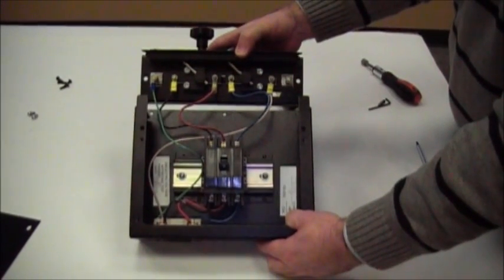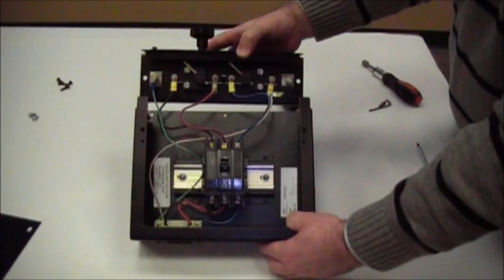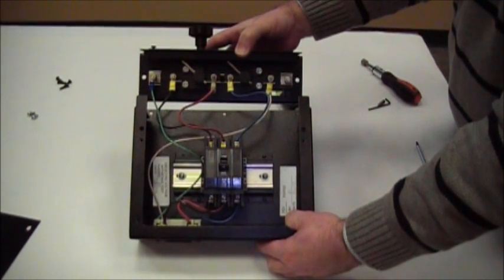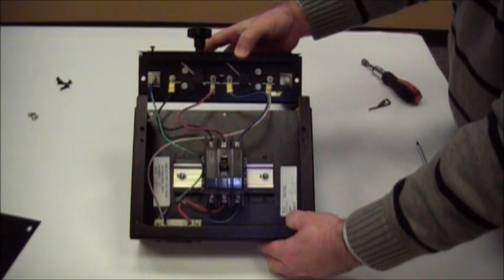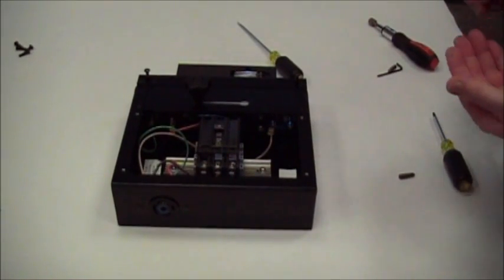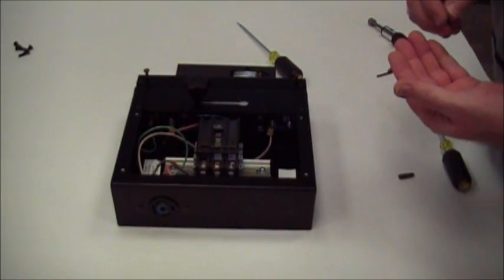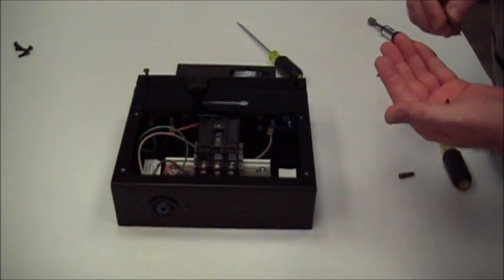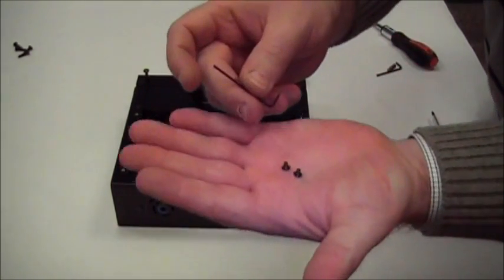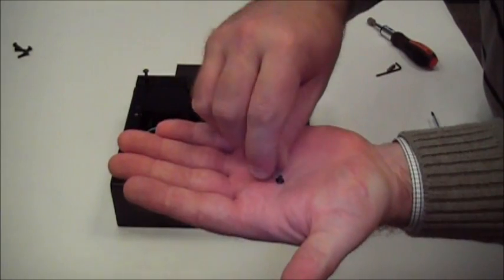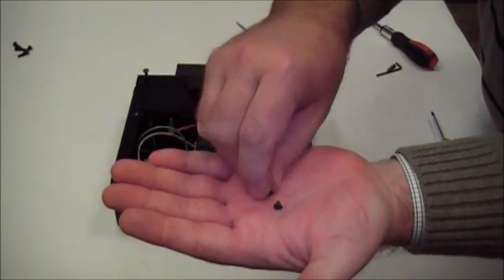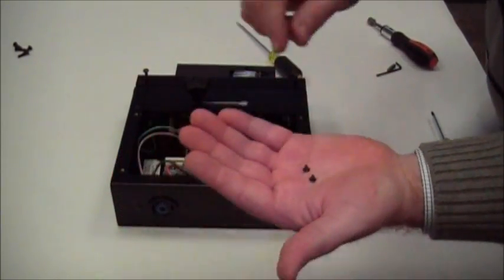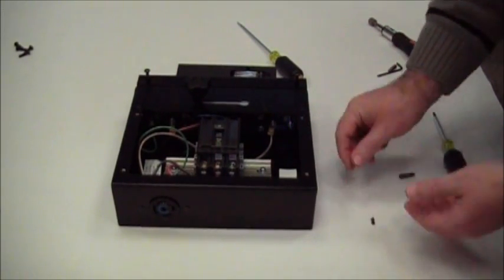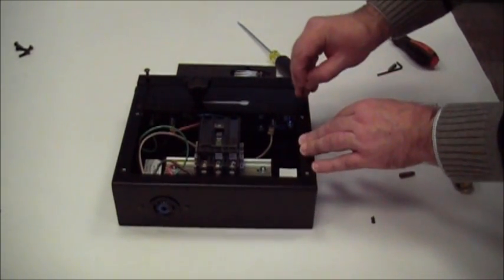The wiring from the paddle to the breaker has been completed, as you can see, and now we'll assemble the paddle mechanism and complete the assembly. To put that assembly on, the first thing to do is get the assembly lined up, and then you have to secure it with some very small screws that hold the face of that on and to the rear. So a little difficult task, but we can get those in and complete that assembly.